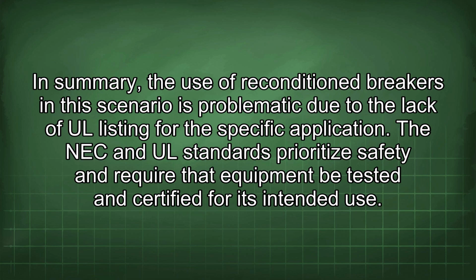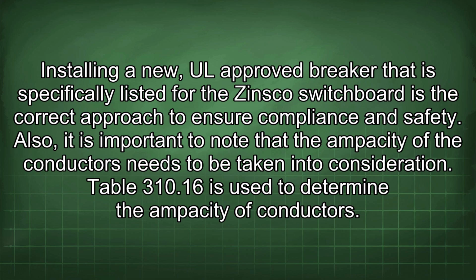In summary, the use of reconditioned breakers in this scenario is problematic due to the lack of UL listing for the specific application. The NEC and UL standards prioritize safety and require that equipment be tested and certified for its intended use. Installing a new UL-approved breaker that is specifically listed for the Zinsco switchboard is the correct approach to ensure compliance and safety.